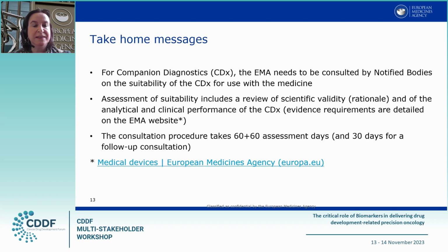Now, if you look at take-home messages for companion diagnostics, the EMA needs to be consulted by notified bodies on the suitability of the companion diagnostic for use with the medicine. The assessment of suitability includes the review of scientific validity, the rationale, and the analytical and clinical performance of the companion diagnostic. And as I mentioned earlier, the consultation procedure takes 60 and another 60 assessment days, and more information you find here on our website.